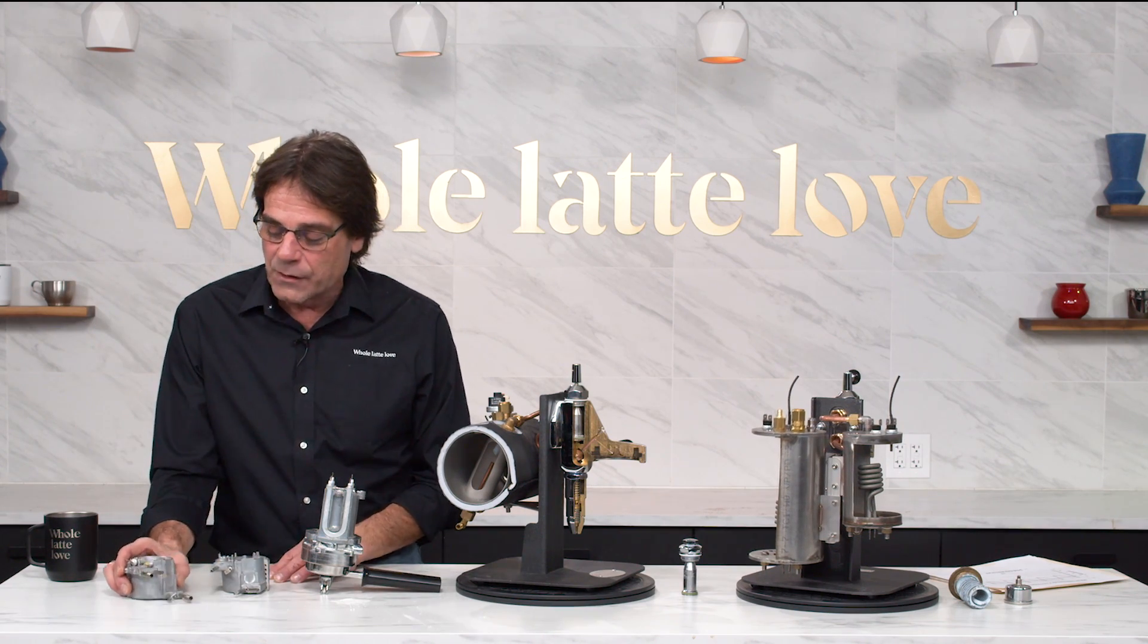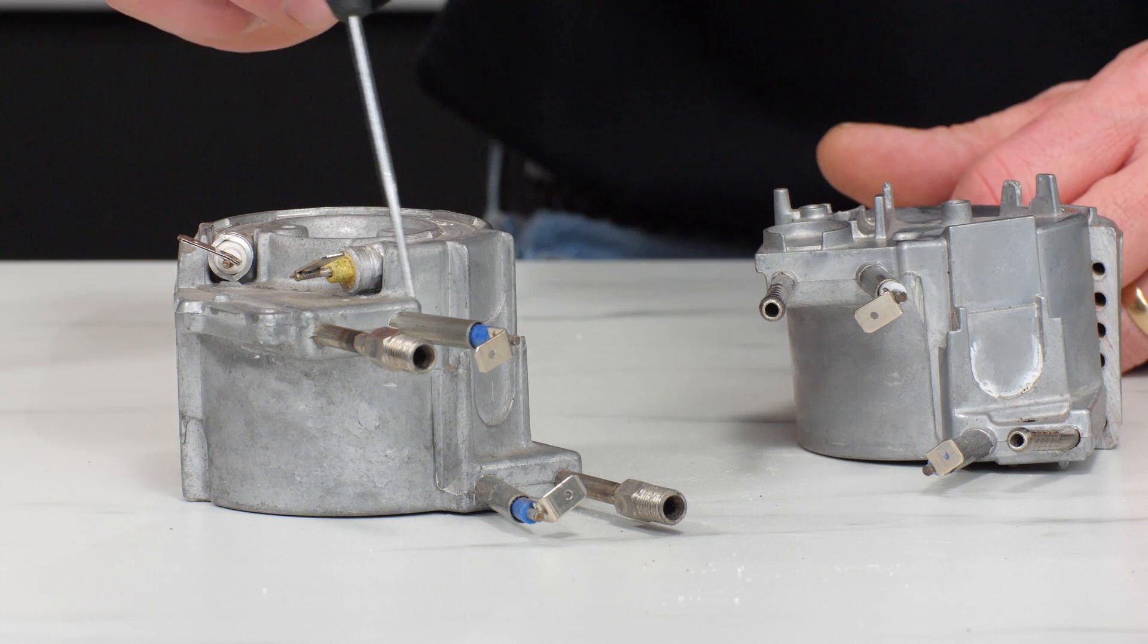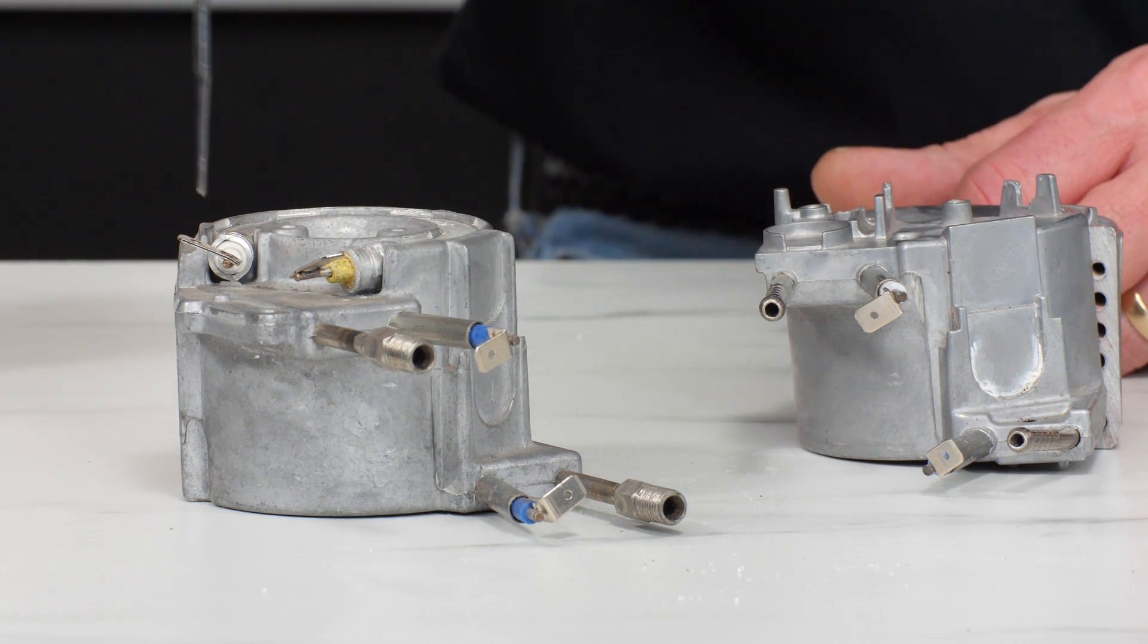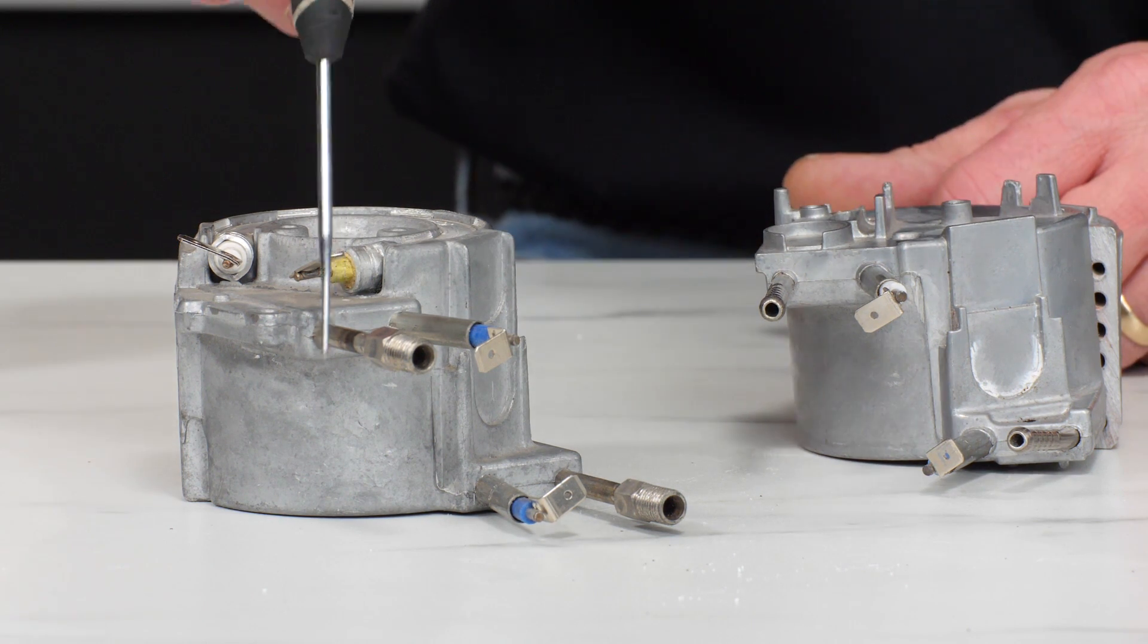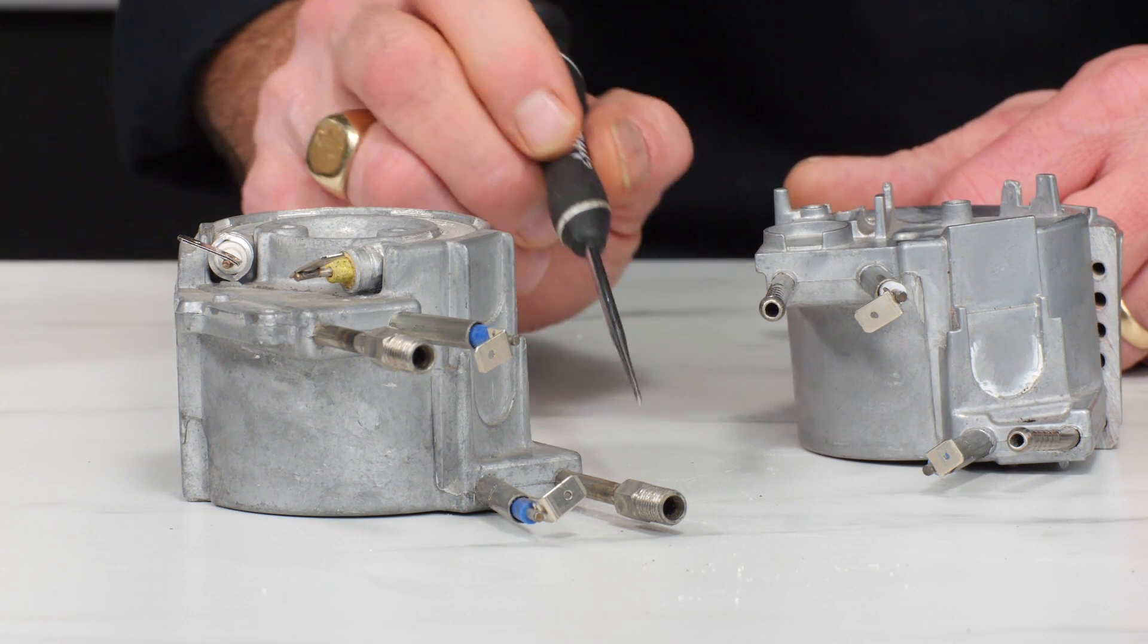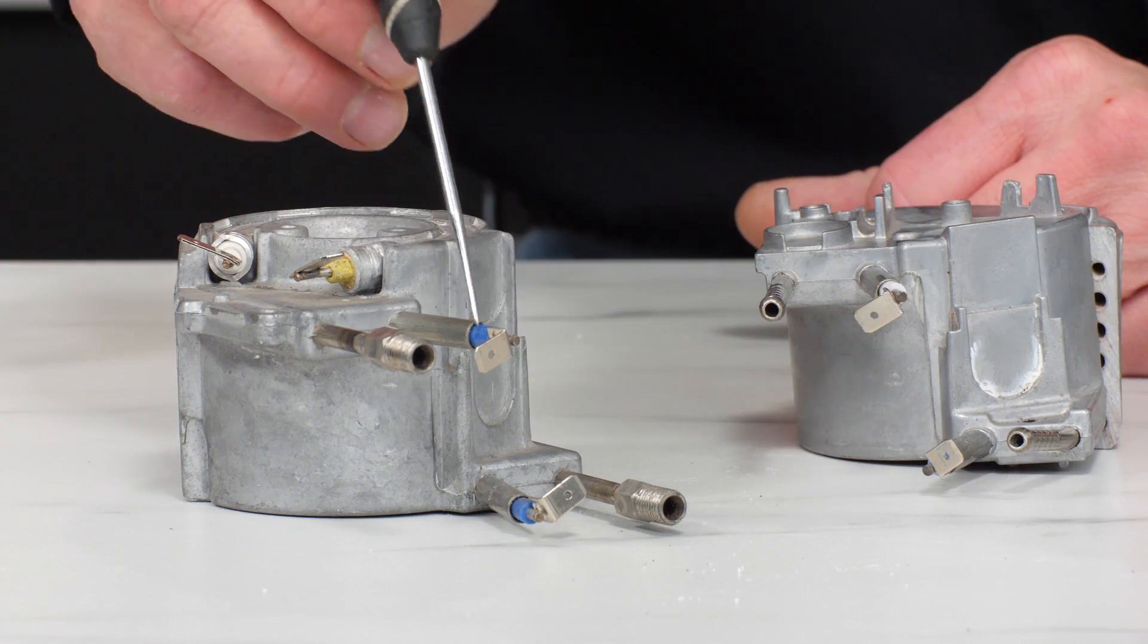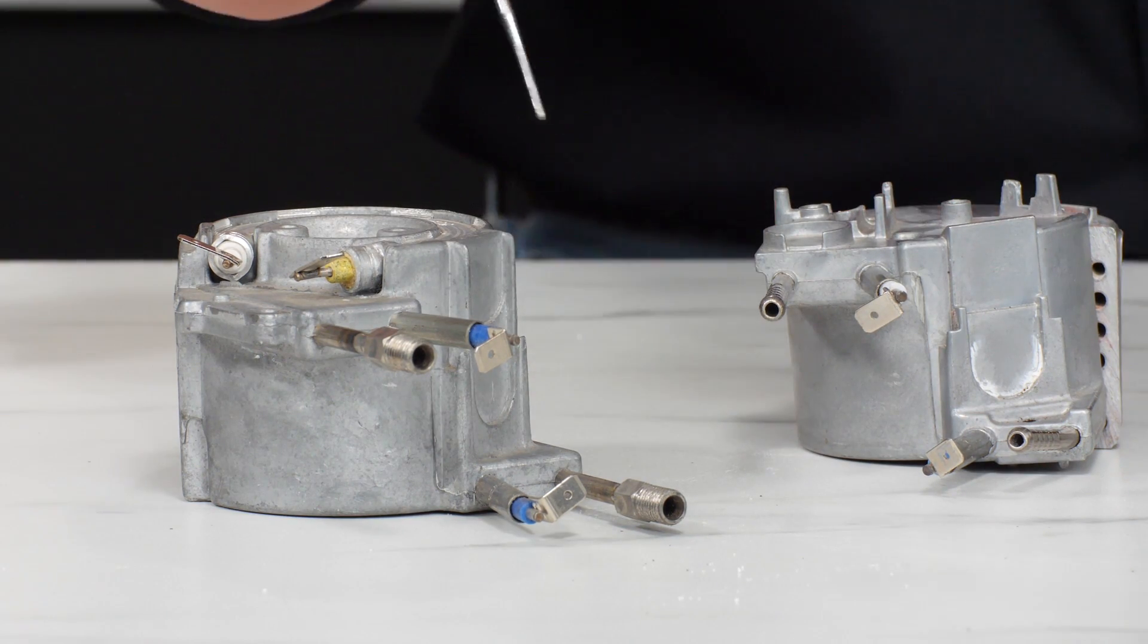There's basically a block of aluminum and inside water's gonna come in one of these pipes and out the other one and it spirals through inside of this aluminum block. These pipes are generally stainless steel that run through inside that aluminum block and then there's a heating element that's embedded in the boiler that heats the water.